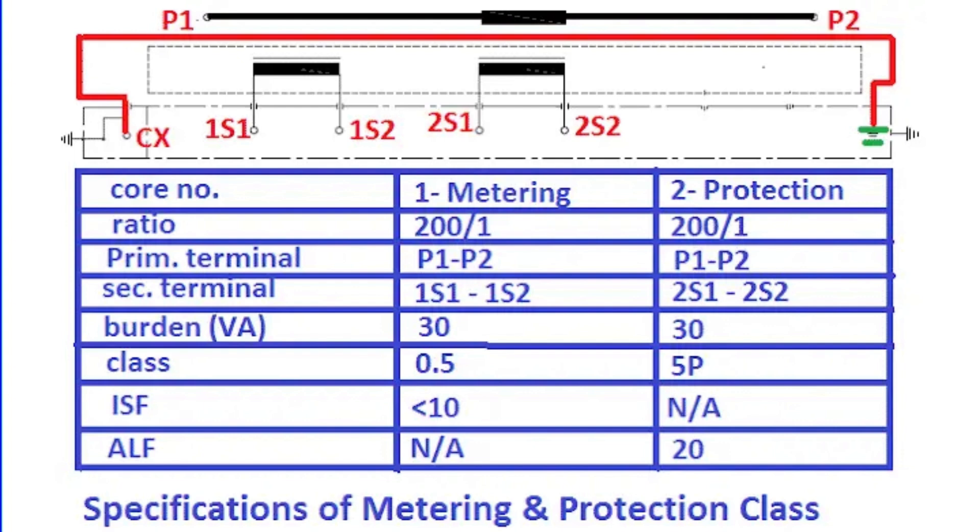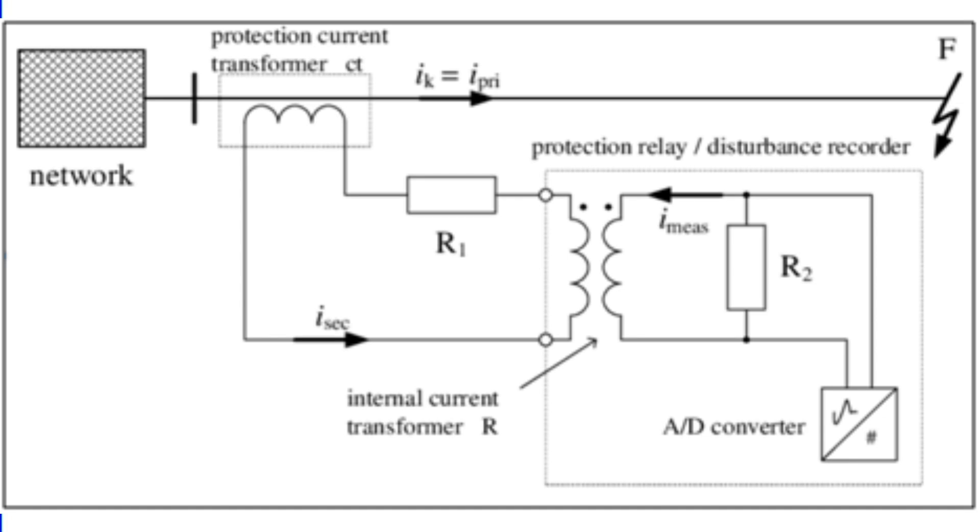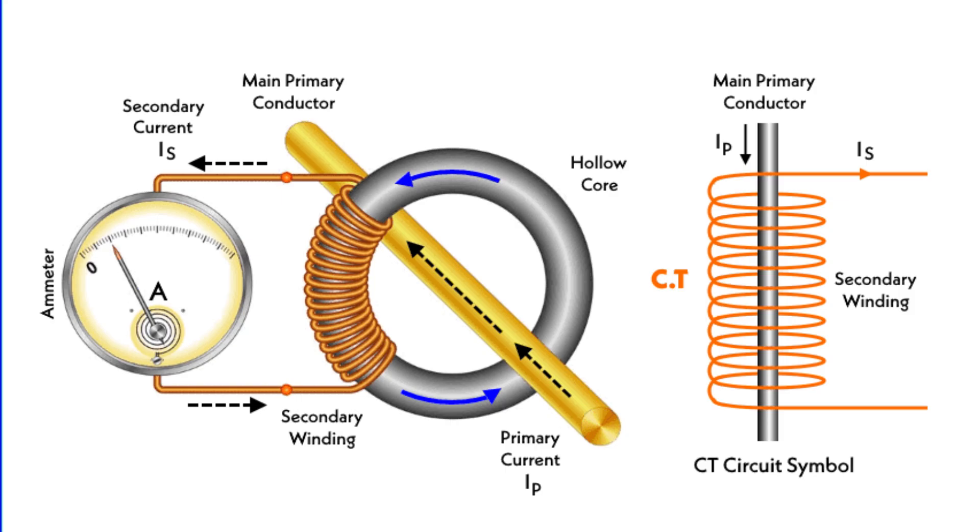However, if a metering CT is used for protection purposes, the core will saturate during fault conditions, distorting the secondary current. This could cause the relay to malfunction, jeopardizing the power system stability. In simple terms, metering CTs are designed to protect meters, not to handle the critical demands of relays during faults.